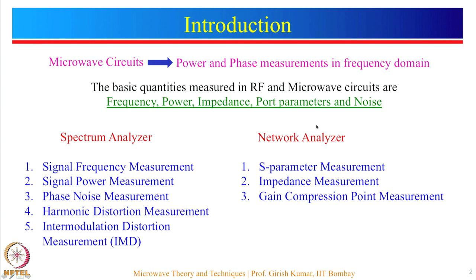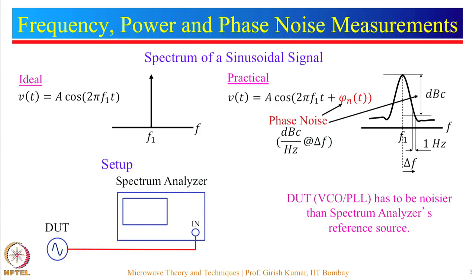Network analyzers are used for S parameter measurements primarily. They can also be used to measure the impedance of a network, which is the input or output impedance. They are also used to measure the gain compression point, which is P1dB of a network. Let us see how frequency, power and phase noise can be measured using a spectrum analyzer.